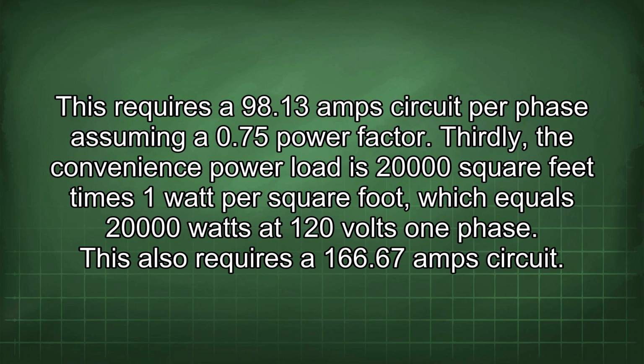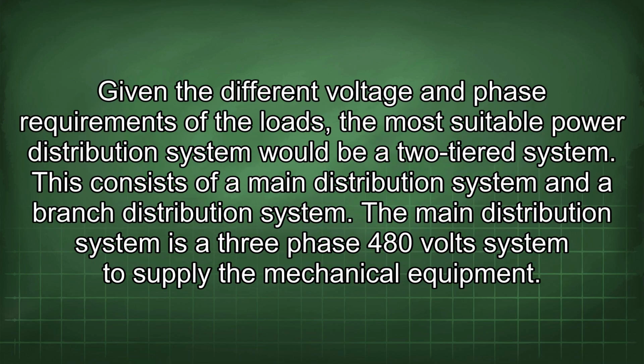Thirdly, the convenience power load is 20,000 square feet times 1 watt per square foot, which equals 20,000 watts at 120 volts 1 phase. This also requires a 166.67 amp circuit. Given the different voltage and phase requirements of the loads, the most suitable power distribution system would be a two-tiered system. This consists of a main distribution system and a branch distribution system.